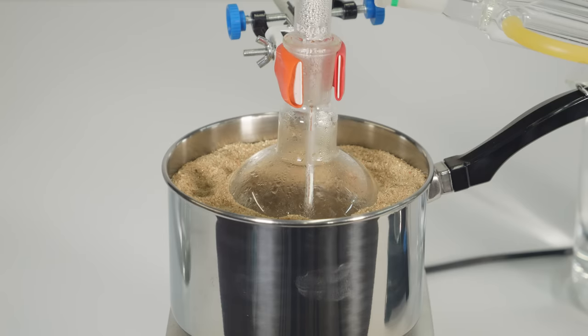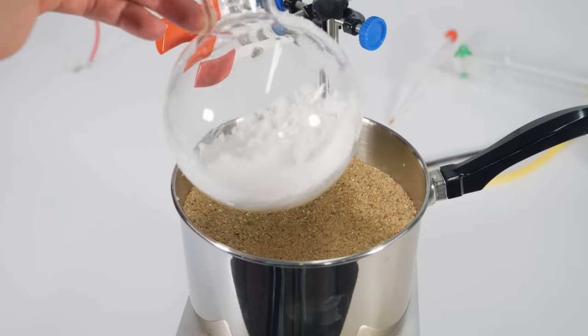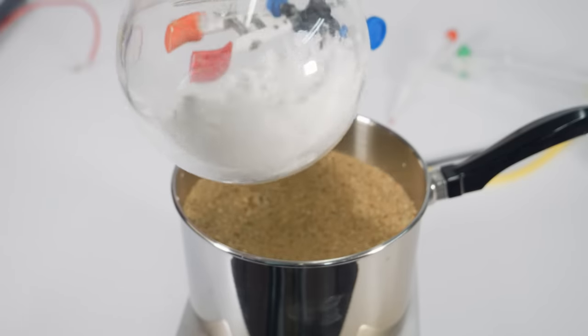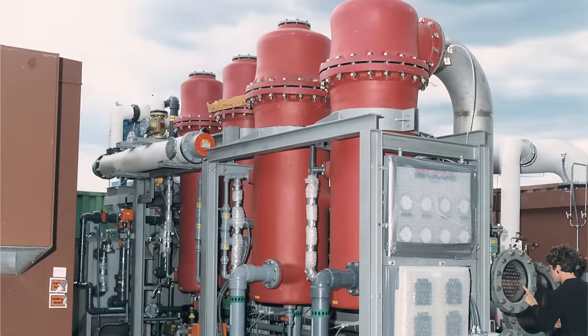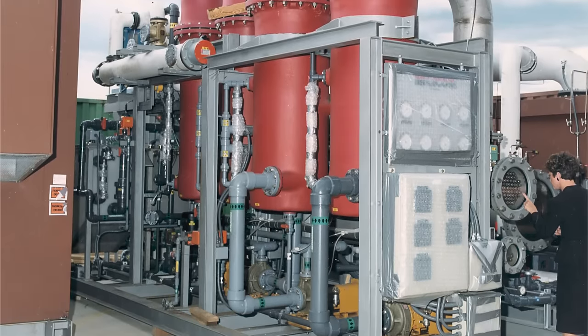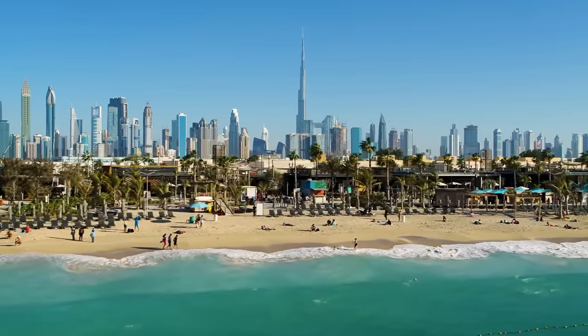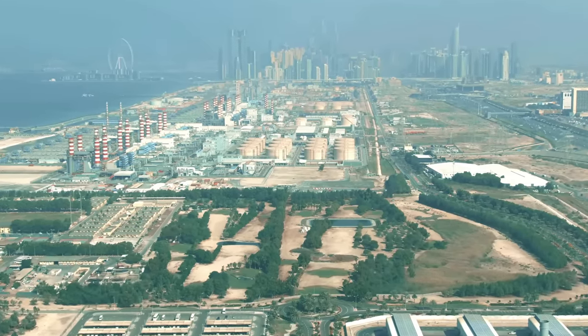But the thermal efficiency isn't the only challenge with distillation. You can see the salt deposits building up in the flask that held the seawater, even after distilling only a small amount of water. These scale deposits reduce the efficiency of boiling because heat doesn't transfer through them very easily, which means they would have to be cleaned off regularly. One alternative is a flash evaporator that sends the liquid stream through an expansion valve to force it to evaporate at temperatures lower than boiling, which minimizes the buildup of scale. Flash evaporators are the workhorses of desalination plants that use distillation, especially in the Middle East, where plants like this have been reliably producing fresh water for decades.